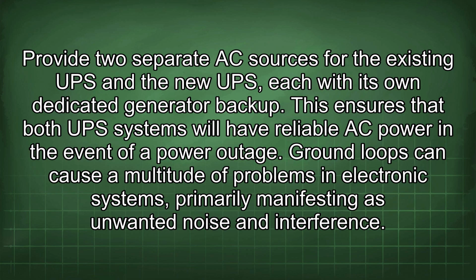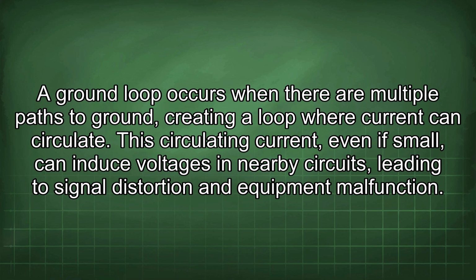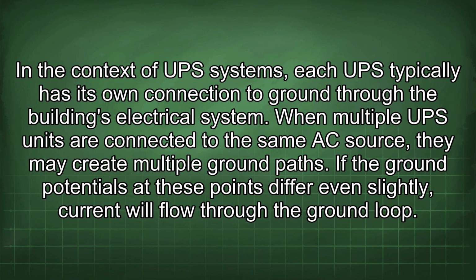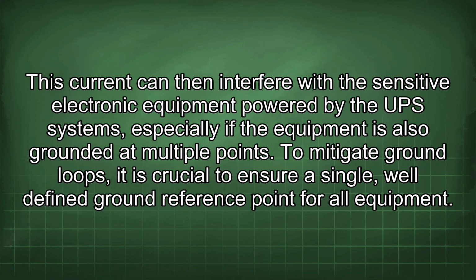Ground loops can cause a multitude of problems in electronic systems, primarily manifesting as unwanted noise and interference. A ground loop occurs when there are multiple paths to ground, creating a loop where current can circulate. This circulating current, even if small, can induce voltages in nearby circuits, leading to signal distortion and equipment malfunction. In the context of UPS systems, each UPS typically has its own connection to ground through the building's electrical system. When multiple UPS units are connected to the same AC source, they may create multiple ground paths. If the ground potentials at these points differ even slightly, current will flow through the ground loop. This current can then interfere with the sensitive electronic equipment powered by the UPS systems, especially if the equipment is also grounded at multiple points.